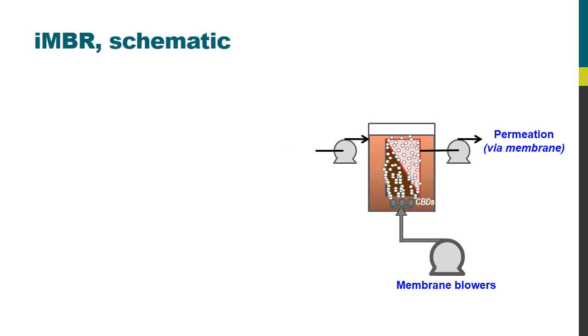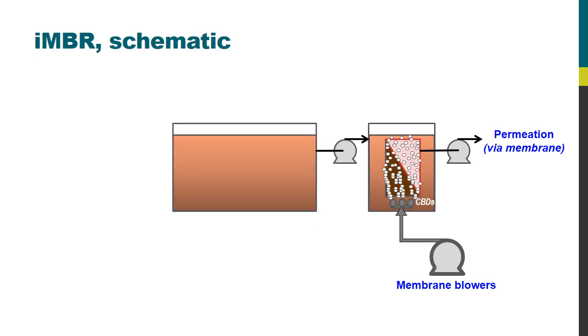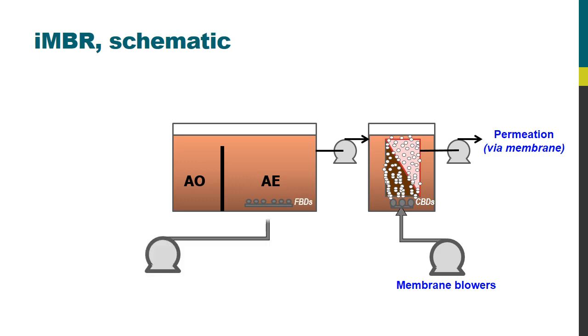That sludge has to come from somewhere, and it is from the biological process tank, which is normally divided into two zones: an anoxic zone and an aerobic zone. There are two different biochemical functions going on in those two zones. The aerobic zone is fitted with fine bubble diffusers supplied from the process air blowers, and that generates a stream of fine bubbles of air whose primary purpose is to provide the microbiology with the oxygen needed for them to survive.